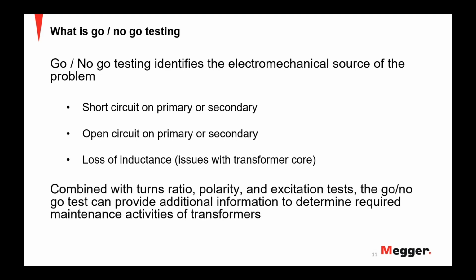And when you combine this with the turns ratio test that I talked about before, where you can see if the transformer is additive or subtractive, and then you get the excitation current, the amount of current that's drawn under that no load test of the turns ratio, this go, no go test will again allow you to pinpoint where issues exist, so that way you can have better informed maintenance activity decisions for your transformers.